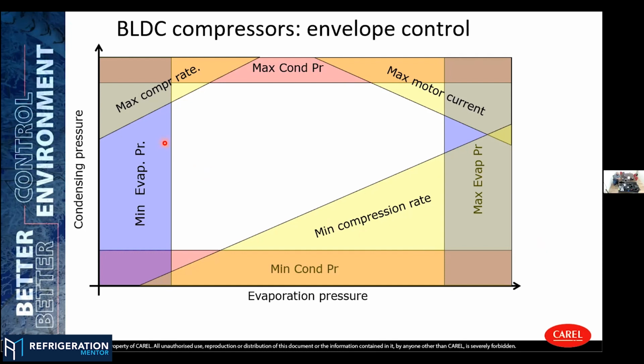Sure. Every time you go out of the envelope, the controller will try to force you back to the center for like 3 minutes. So let's say that we are at the minimum evaporation temperature. For 3 minutes, the system will do all it can in terms of decelerating the compressor and opening the electronic expansion valve in order to force the operation point to the safe zone. If it is not possible, it will trigger an alarm, and this alarm will stop the compressor for like 5 minutes. It is a time to make the technician aware that we have a problem, and it will show you a minimum evaporation pressure alarm. And after 5 minutes, it will start again.